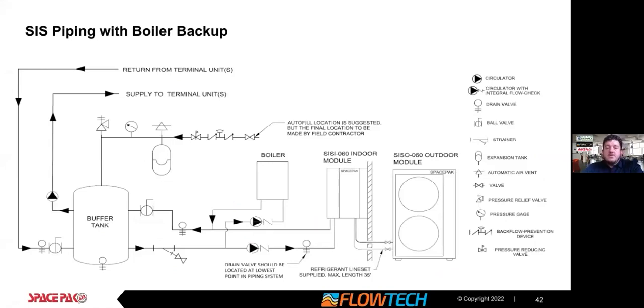So this is showing some other, and we have other design slides we'll get to as well, but this is showing adding a boiler, and the boiler is on there for possible backup protection at low ambient. Oftentimes engineers will size the split unit for part load, and they'll catch the really low temperatures with a backup boiler. Some folks like to see a backup boiler on there for redundancy as well, so they have another source that they're not only relying on one piece of equipment.